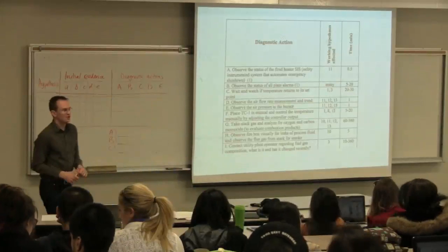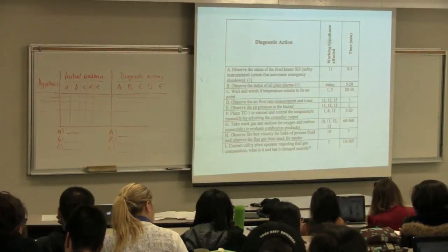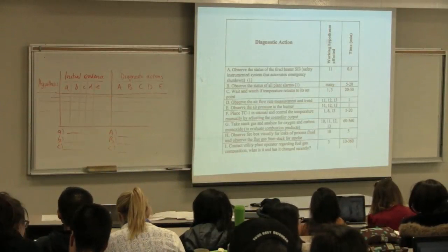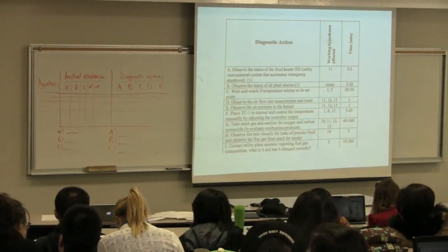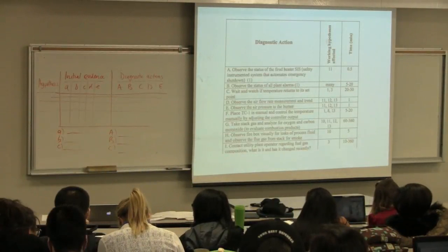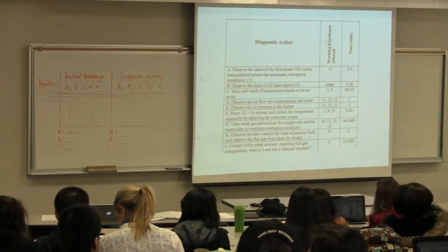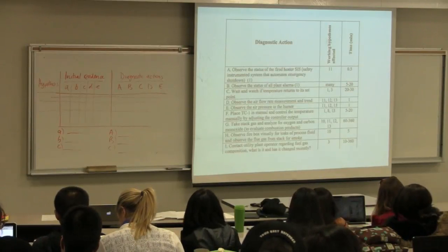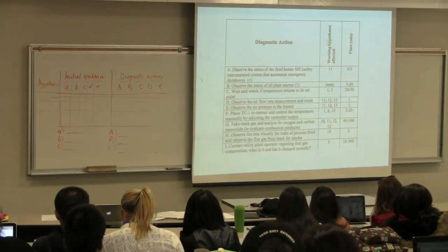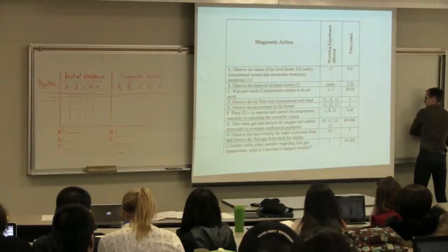Remembering here, the issue is that we've got the temperature dropping and the fuel rate rising. And we discussed in yesterday's class that's counter to our expectation. Our expectation is that if the temperature is dropping, the fuel needs to be going up with automatic control. But when that fuel goes up, we expect to see the temperature also start to go up eventually. So from a feedback control perspective, that initial part of the graph makes sense, but not the second half. Let me put that up here just so it's clear.